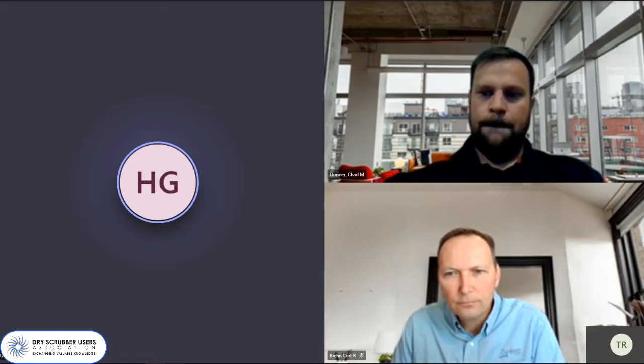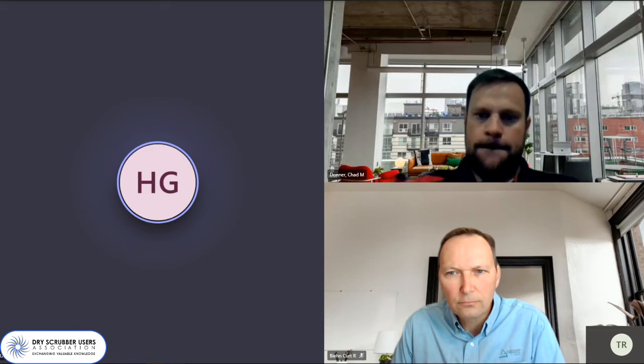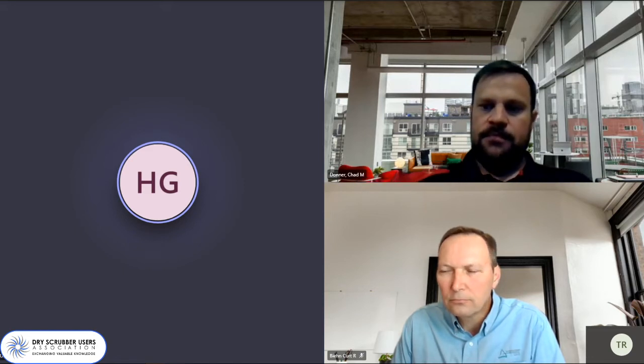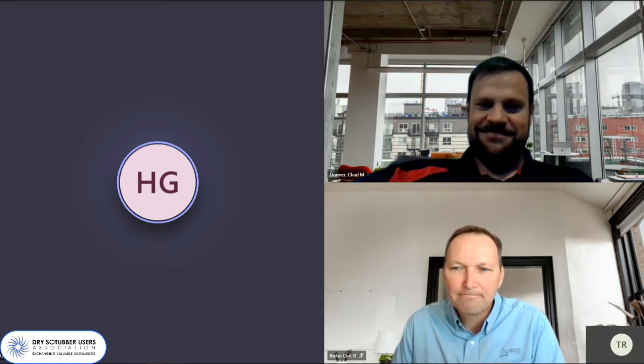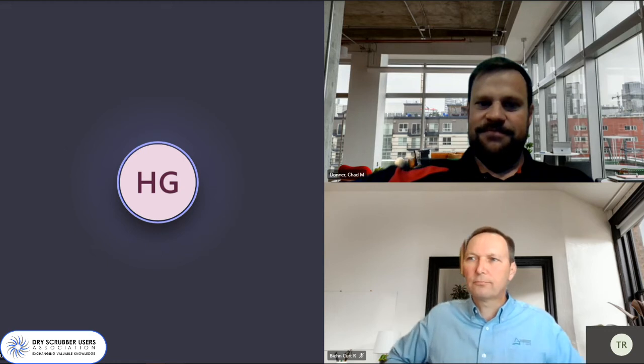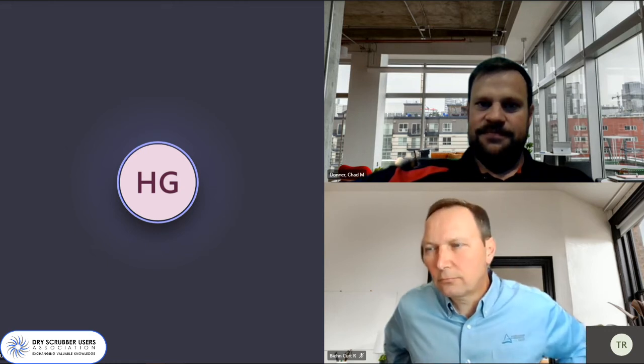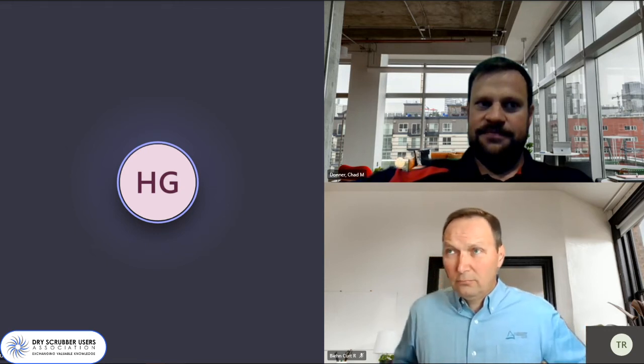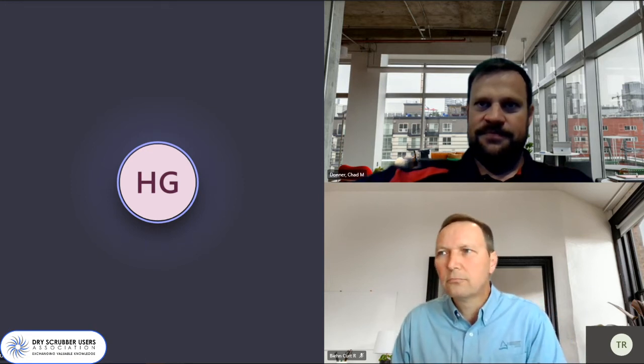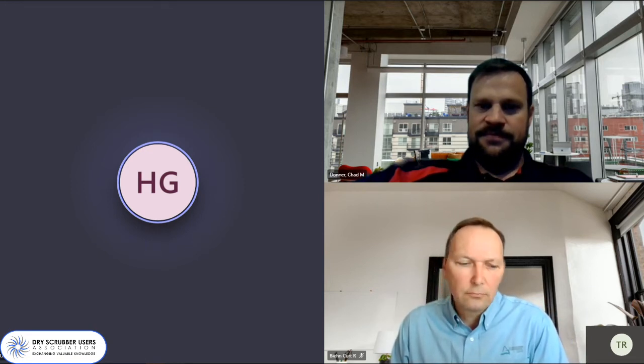One question I had, I always have this question at a plant and I very rarely get a good answer on it. So I'm interested if you've got something to share. Obviously the desiccant wheel dryers are an integral piece to controlling the relative humidity. Do you have any recommendations or advice for people with those on how they can monitor and tell that they're doing what they need to do, or that they need to be serviced, or any kind of indicator? Because as you noted, if they're not operated properly, they can cause more harm than good.